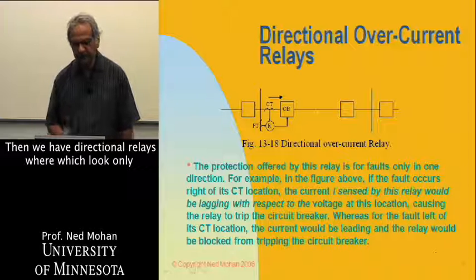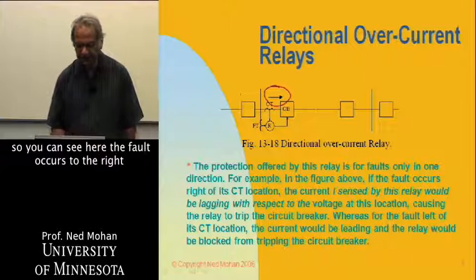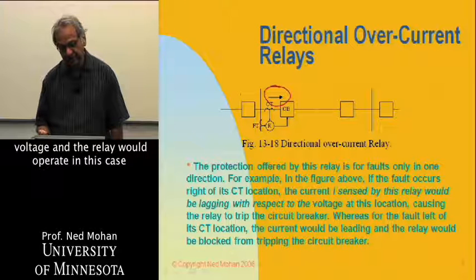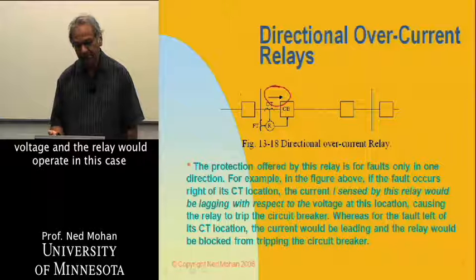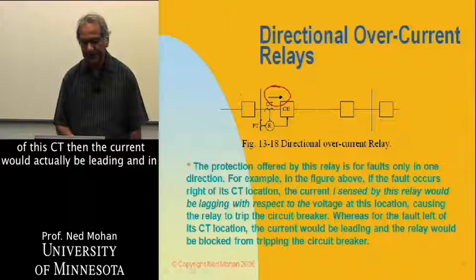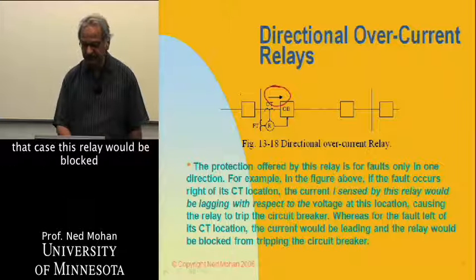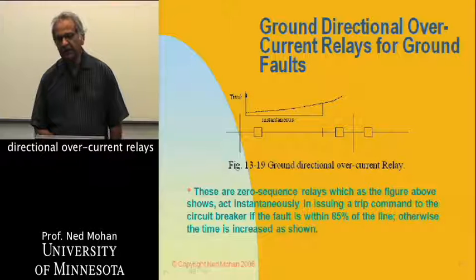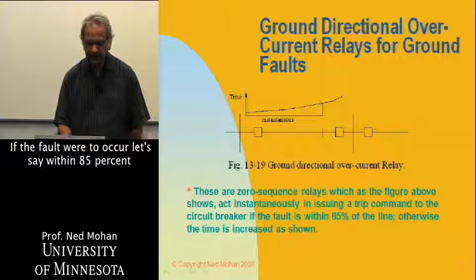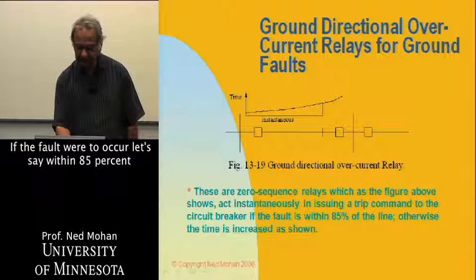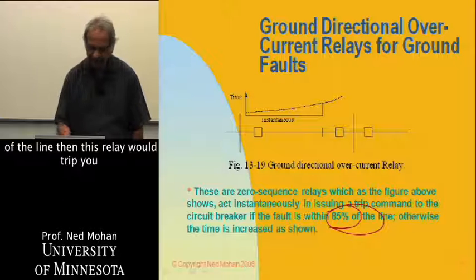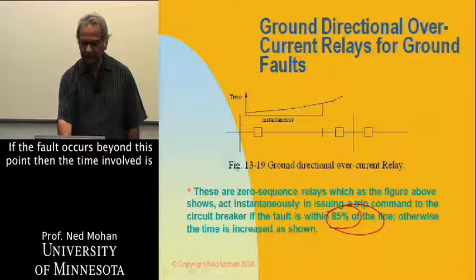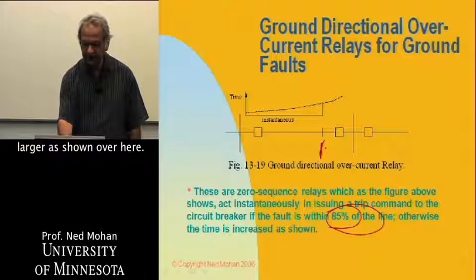Then we have directional relays, which look only in one direction. If the fault occurs to the right of the CT, the current would be lagging the voltage and the relay would operate. If the fault occurs to the left of the CT, the current would be leading, and in that case the relay would be blocked from tripping the circuit breaker. Then we have ground directional overcurrent relays for ground faults. If the fault occurs within 85 percent of the line, this relay would trip instantaneously. Otherwise, there is a time delay — if the fault occurs beyond this point, the time involved is larger.